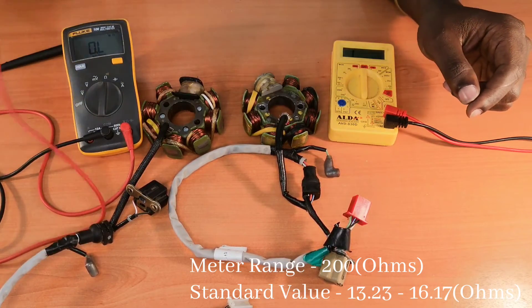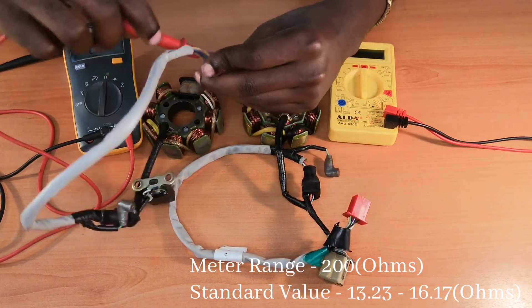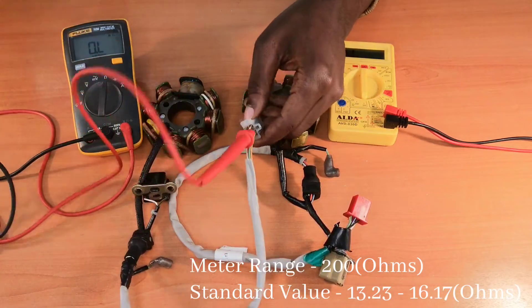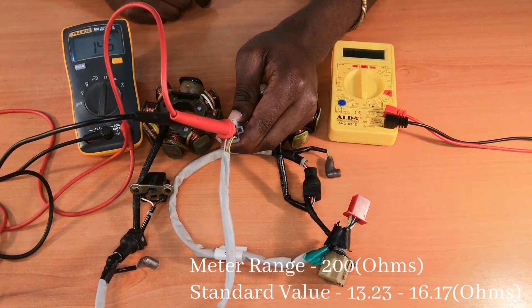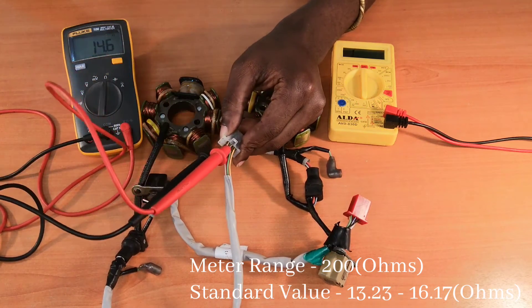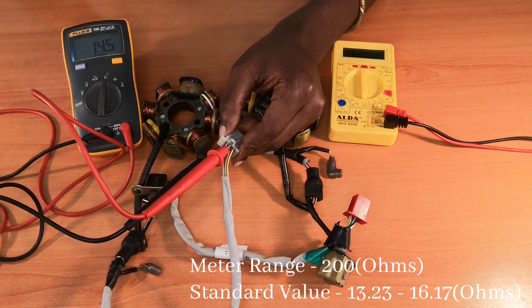I'll take my positive lead to this red corded wire. I'm checking the exciter coil resistance, and then the negative lead to the black-yellow wire. The result should be between 13.23 and 16.17 ohms, and as you can see, my multimeter is displaying 14.5. That means this exciter coil for this stator coil is okay.